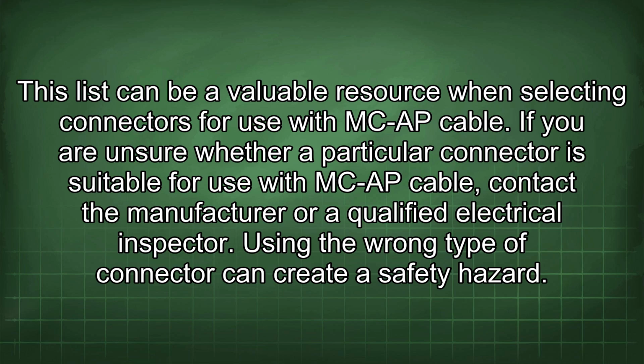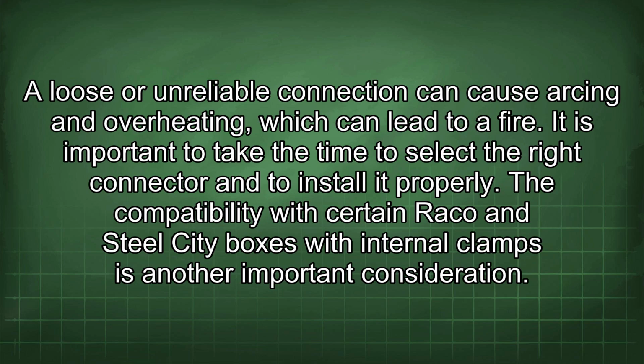If you are unsure whether a particular connector is suitable for use with MCAP cable, contact the manufacturer or a qualified electrical inspector. Using the wrong type of connector can create a safety hazard. A loose or unreliable connection can cause arcing and overheating, which can lead to a fire. It is important to take the time to select the right connector and to install it properly.